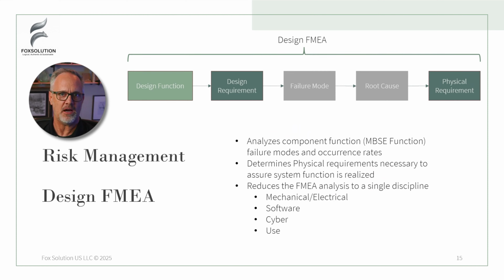So in this case, now we have a design requirement that we're going to analyze for failure modes and root causes driven from design functions that are delivered in one component of the system. Now, this is really necessary because those design requirements are related to different disciplines. Might be software, might be hardware, might be usability. This is where we've assigned it to a particular discipline, so we know which format of design failure mode analysis to put it through. And the reason I say that is when you do a software failure mode analysis, we don't have 20% failure.